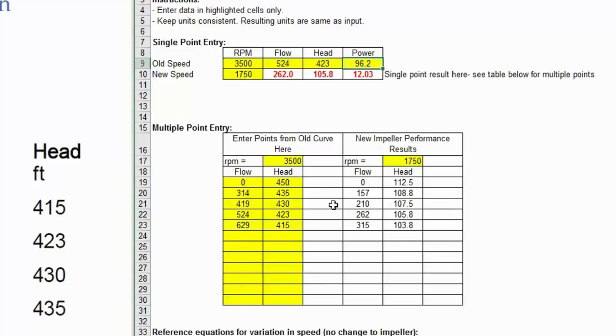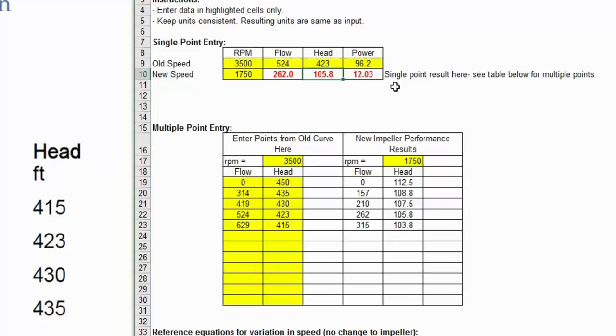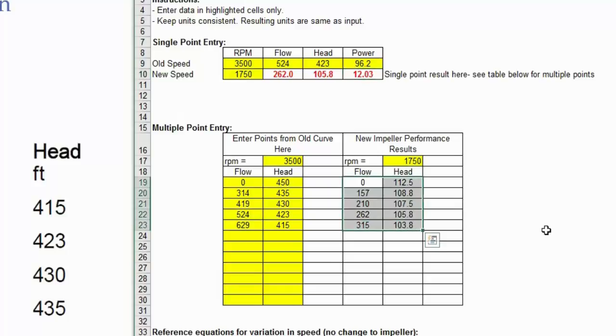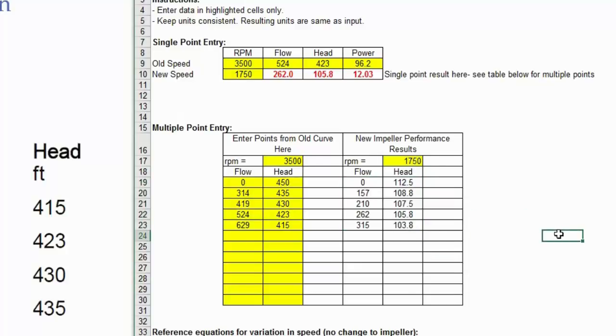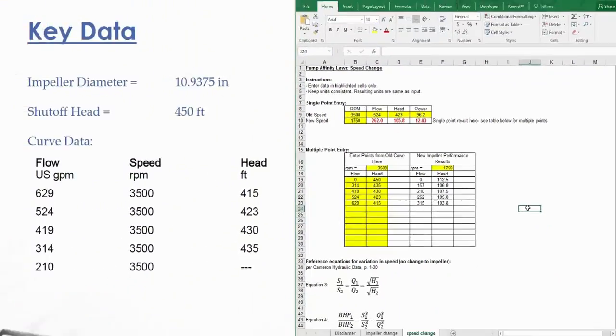So since that's the case, your power and your head show big differences. Look at that: 423 feet of head went down to 105 because head is proportional to the square of speed, and then power is proportional to the cube of speed. Look at that. And now you've got a new pump curve here. You could plot that out and see exactly what your new pump curve would look like at half the speed. That concludes the video on affinity laws. Basically, I'm sure there's plenty of other questions that I haven't covered, but this is just the gist.